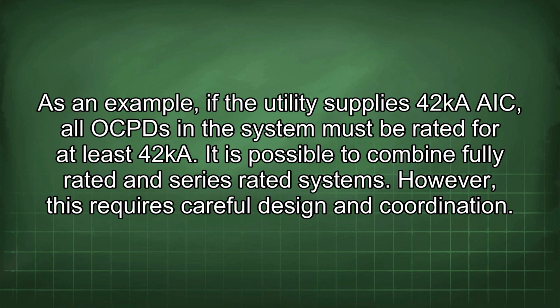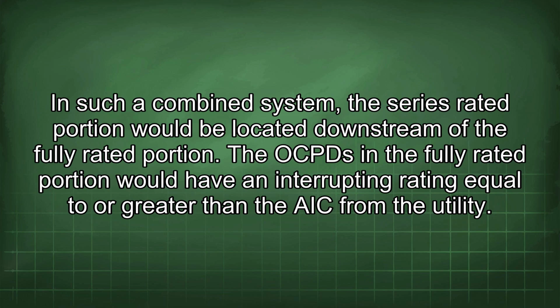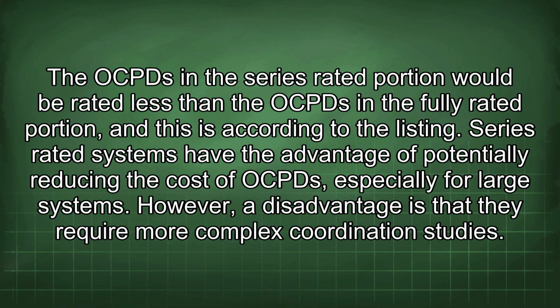However, this requires careful design and coordination. In such a combined system, the series-rated portion would be located downstream of the fully rated portion. The OCPDs in the fully rated portion would have an interrupting rating equal to or greater than the AIC from the utility. The OCPDs in the series-rated portion would be rated less than the OCPDs in the fully rated portion, and this is according to the listing.